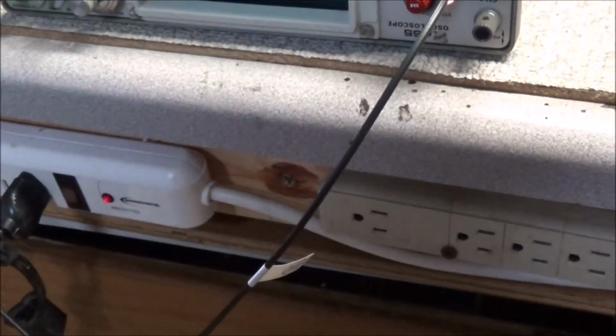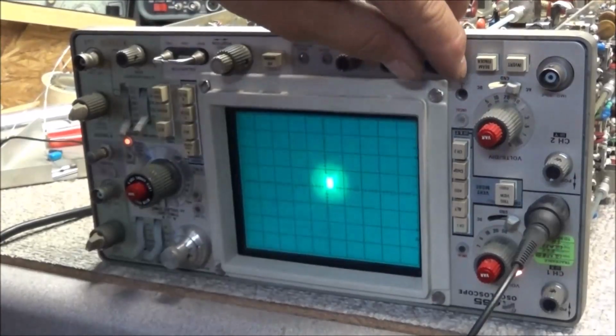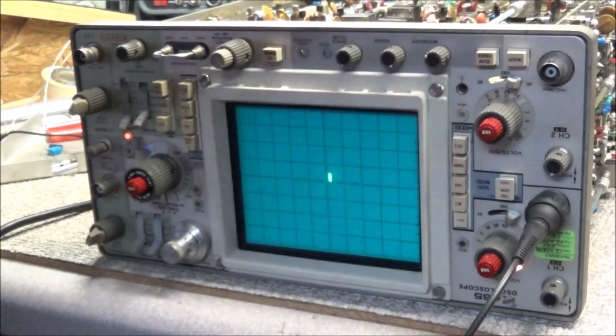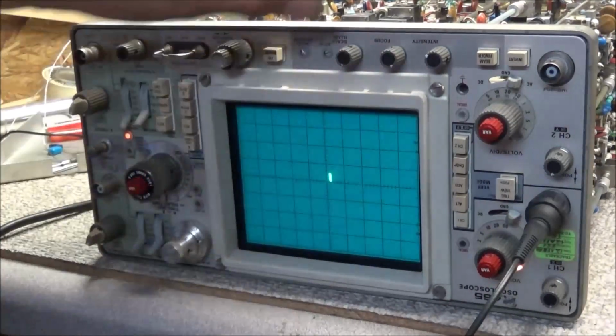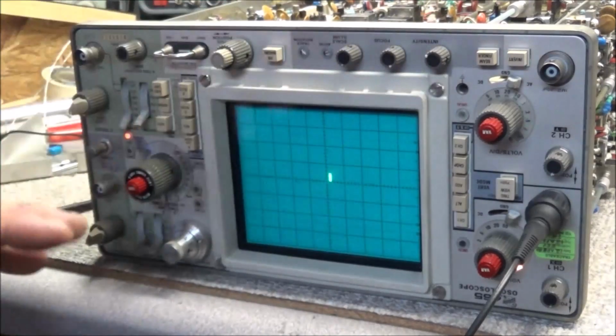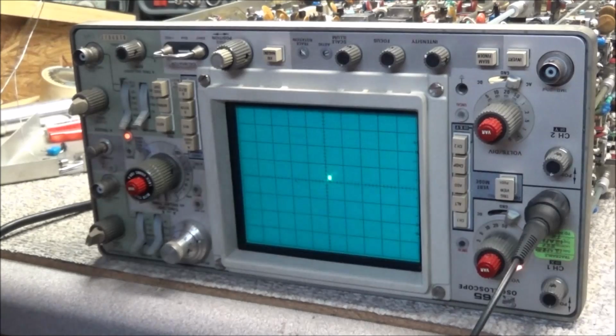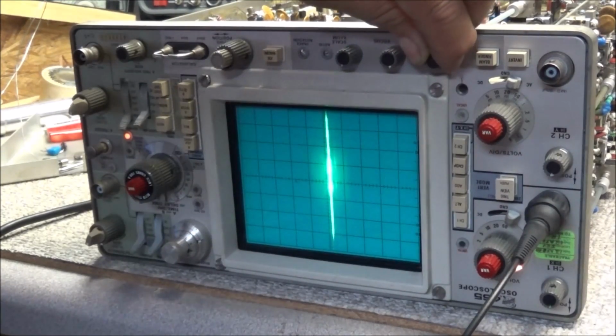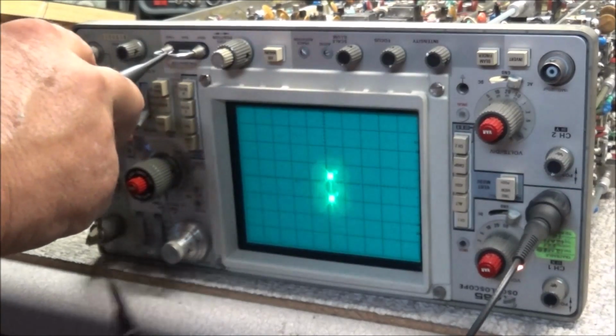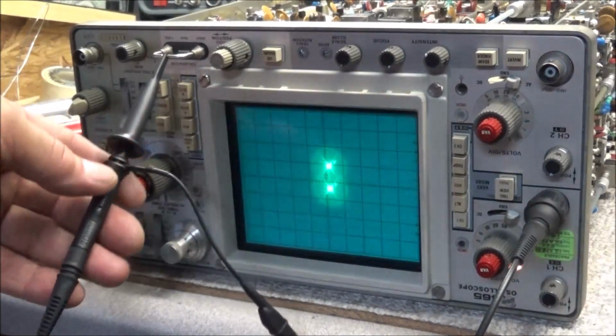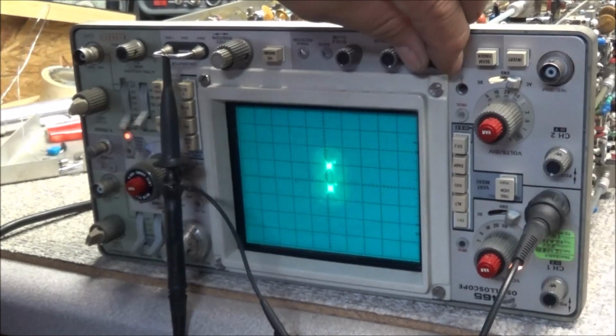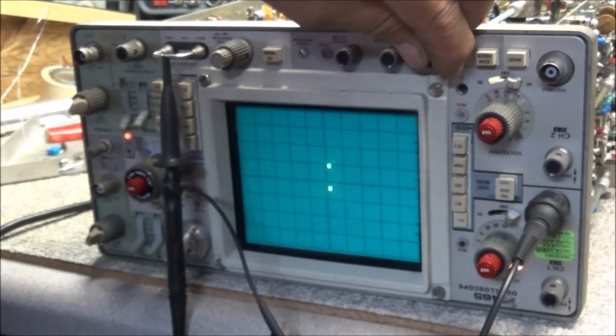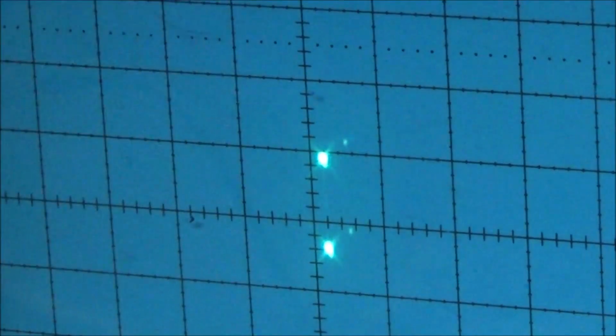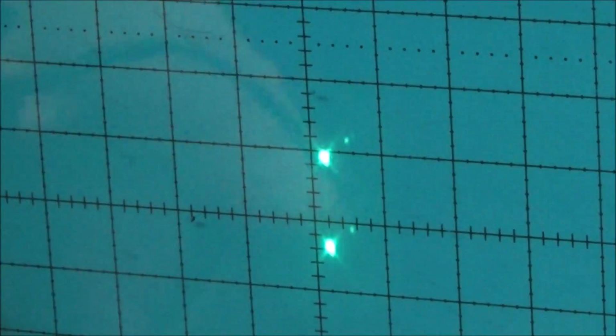Move the camera down. I know it kind of looks a little funky right there, but I'll turn the intensity down a little bit and get rid of that dot. You can see that's a nice pretty trace. It focuses out real good. Well, not actually a trace, but a line there, a dot. Looks real good, and we can see that the probe calibrator is working. That intensity knob is a little funky, but you can see we do have the dot there, and we know the calibrator is working.